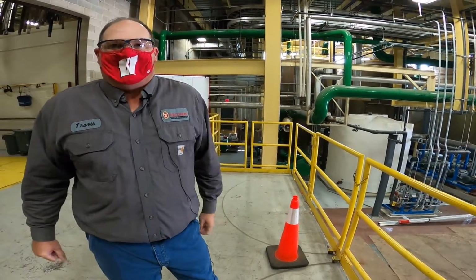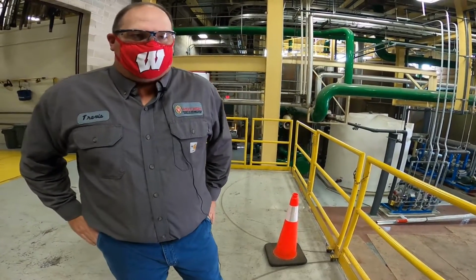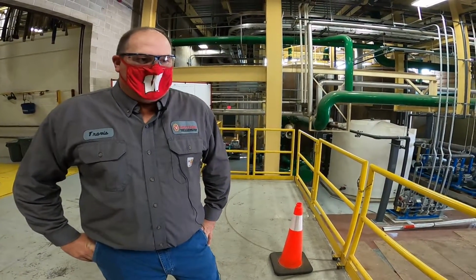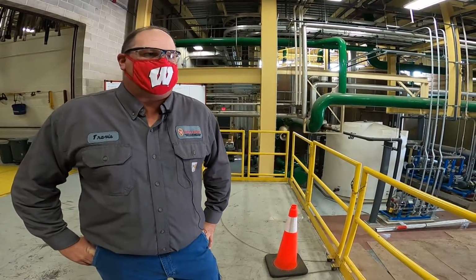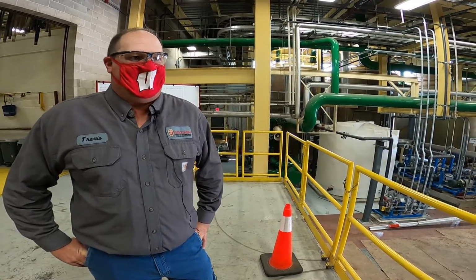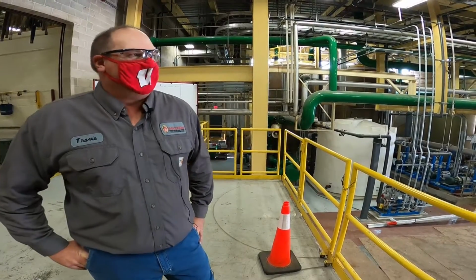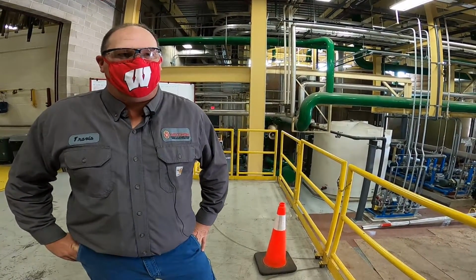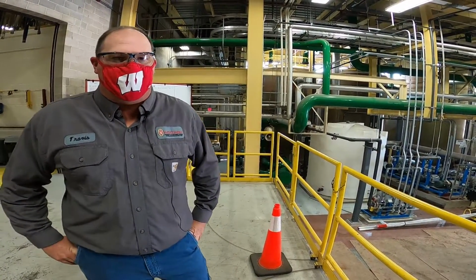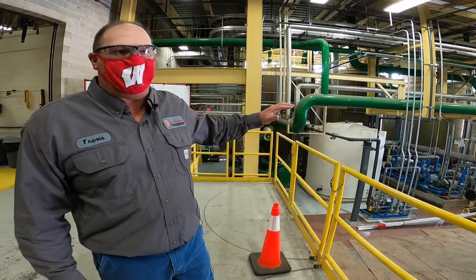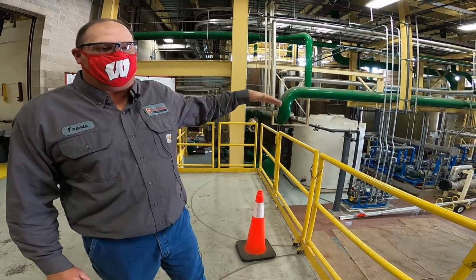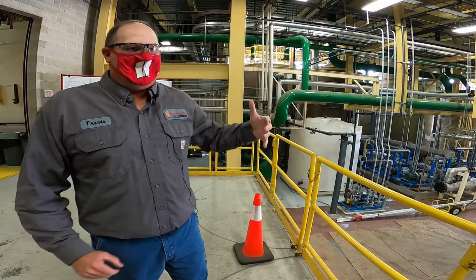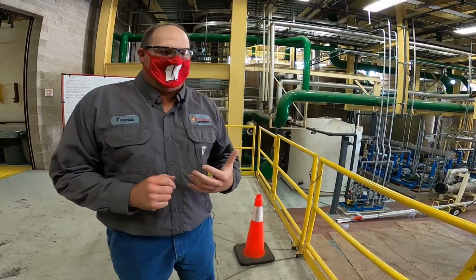Why do you want to minimize the amount of condensate that you lose? How come you want to get as much back as possible? Yeah, I mean, getting it back is, we want to be reliable, we want to be efficient, and it's very expensive to make up. You're looking at probably $15 for every 1,000 gallons of boiler water that's made up with the chemicals and the pumping system and the heat that you got to put into that water.